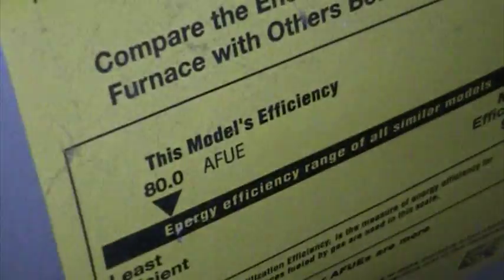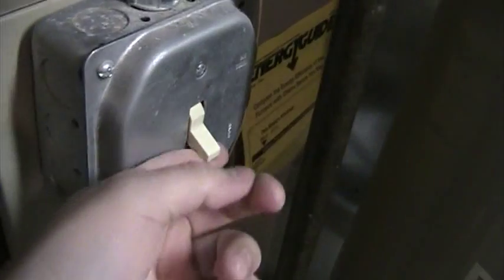So I'm going to start it up and we will hear it. Oh, by the way, 80% efficiency. So I'm going to start it up right now. All right, there goes your draft inducer. This is going. Pressure switch just verified. All right. Now we're waiting for an igniter.